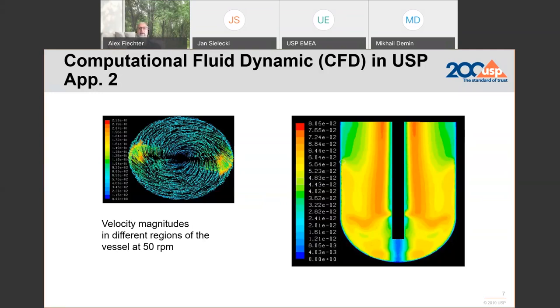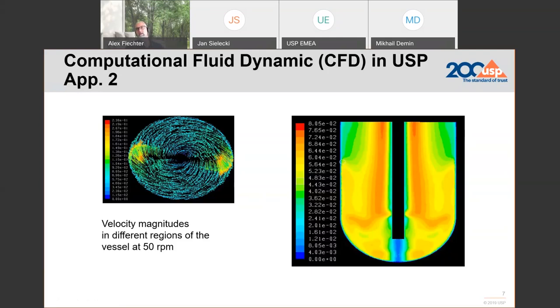Considering that fact, for some dissolution method developers this plays a critical role. Some of them even use peaked vessels in development — vessels with a glass peak or glass bowl — just to redirect the specimen away from sitting beneath the shaft and expose it more to energy and fluid dynamics. For development purposes, this is a useful tool to see early release results. However, for routine quality control and batch release, peaked vessels are no longer within dissolution vessel specifications — I haven't seen any monographs or approved products from FDA or other authorities using them.